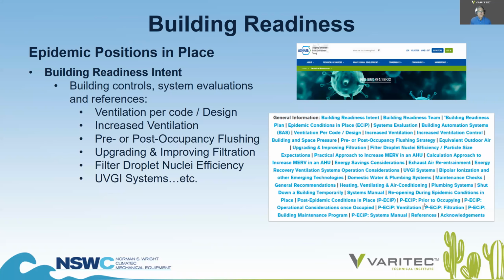The Building Readiness Intent goes on to state that controls and system evaluations are to be evaluated. Just a handful drawn from this listing, I've included here on the left: the ventilation per code design, increased ventilation guidelines, pre or post occupancy flushing, upgrading and improving filtration and what is involved in that, filter droplet nuclei efficiency with regard to MERV filtration listings or certifications, UVGI systems, et cetera, et cetera, et cetera. All of them are laid out here and are inclusive in that epidemic positions in place guideline, offering you guidance for each of those topics.